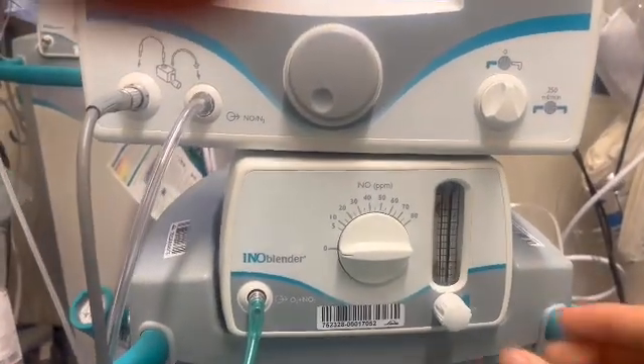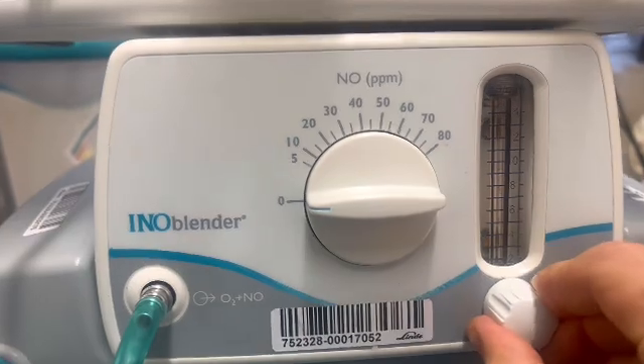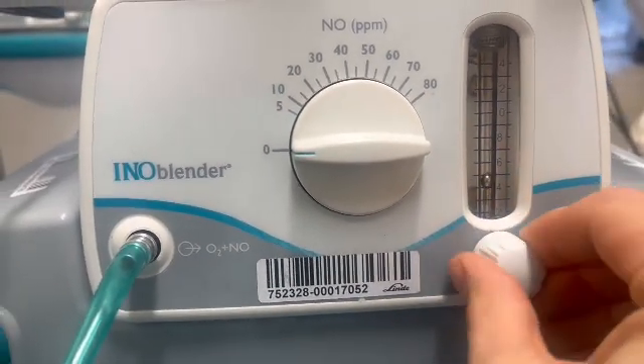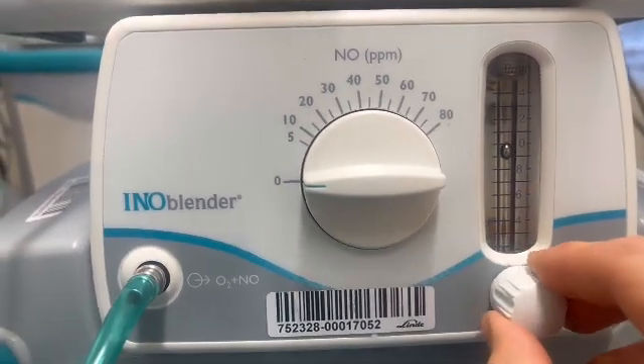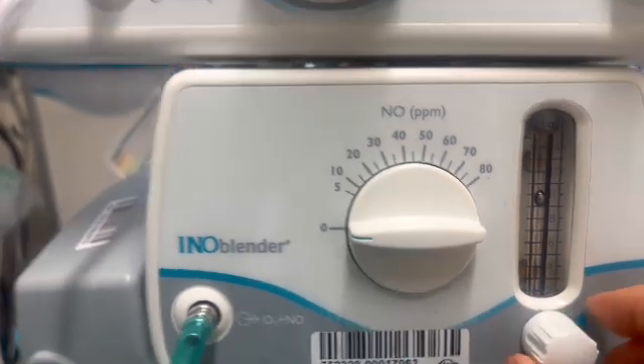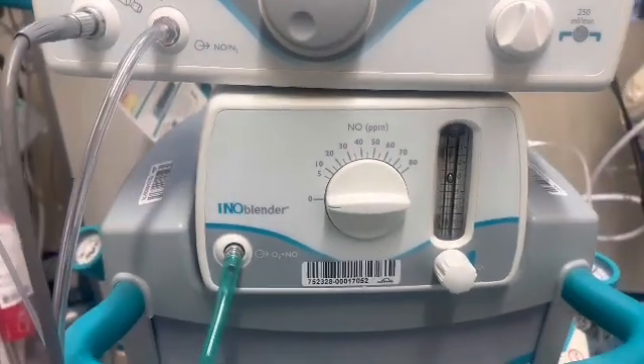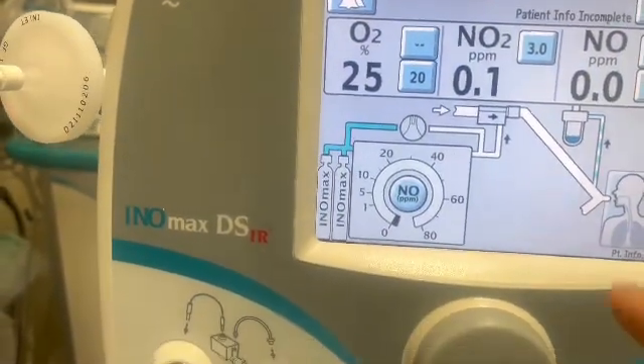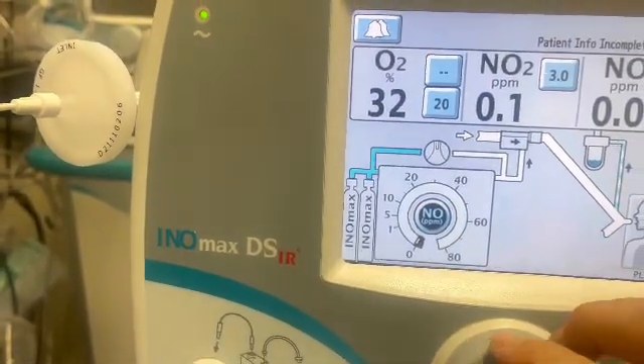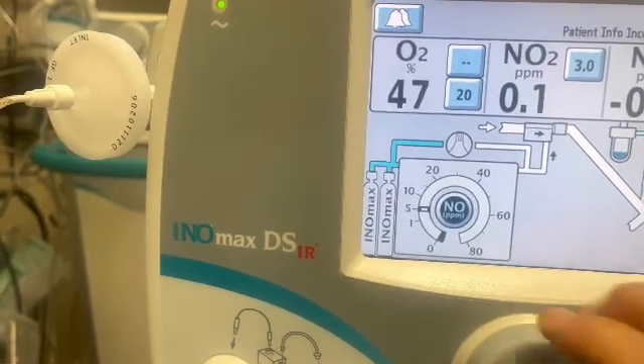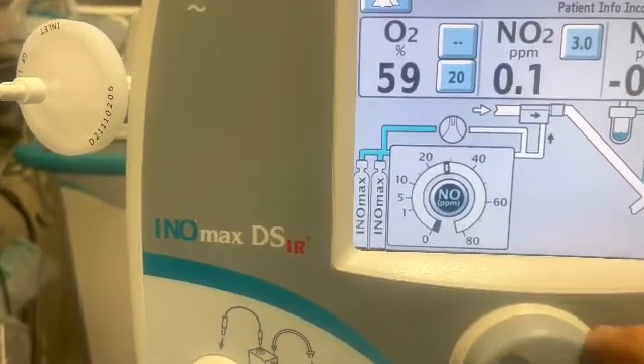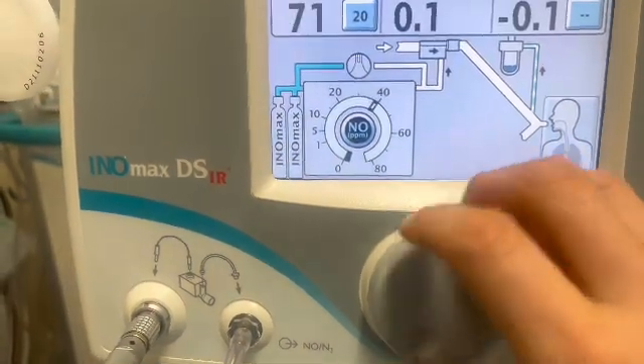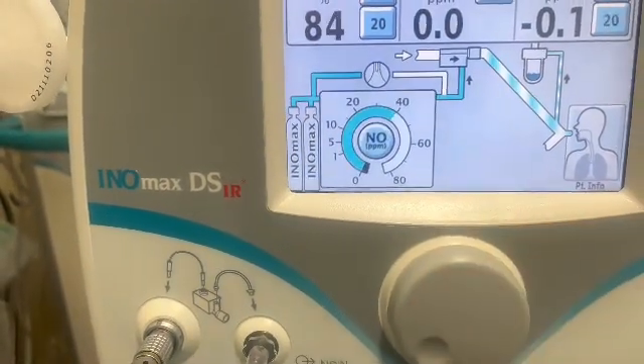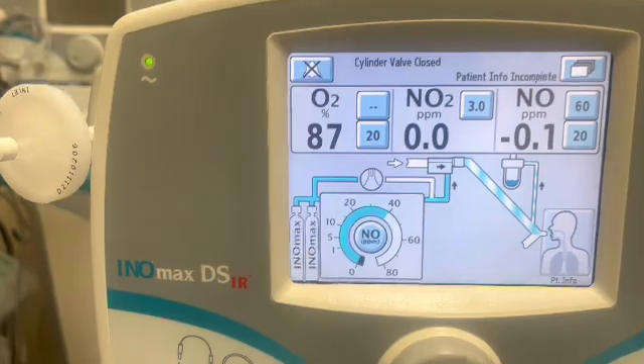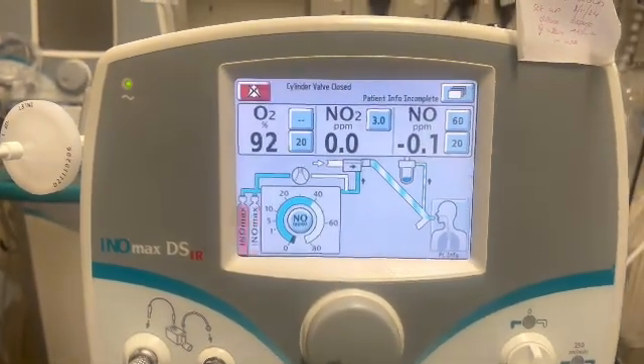Ensure INOmax cylinders are closed. If your test kit is still connected, set the O2 flow meter to 10 litres a minute on the INOblender. Press the middle icon and turn the cursor to 40 parts per million, and press on the cursor to confirm. You should get the cylinder valve closed alarm.